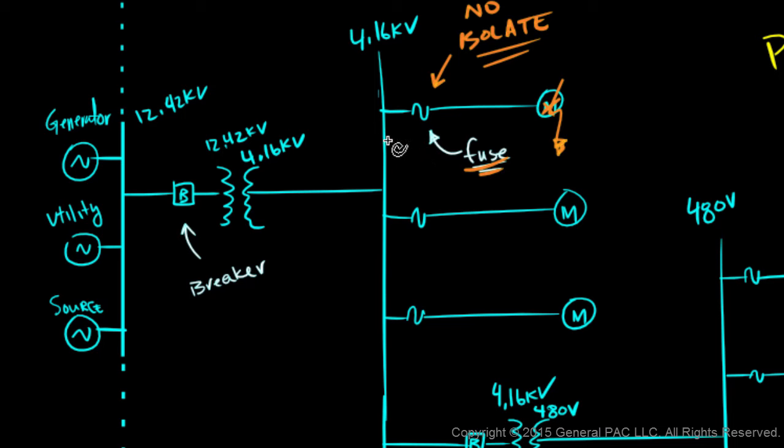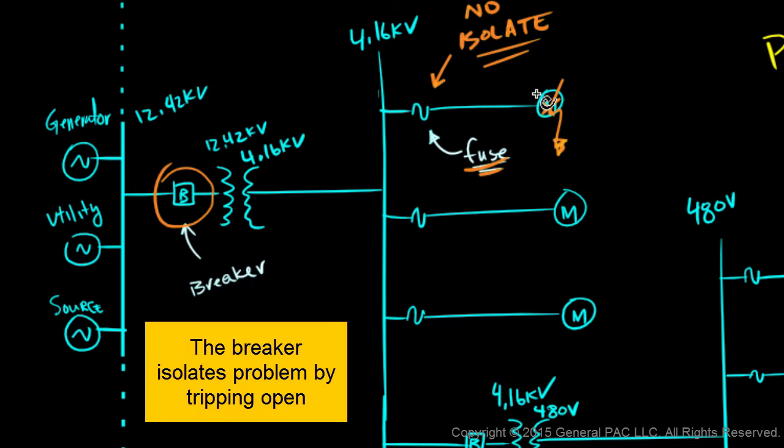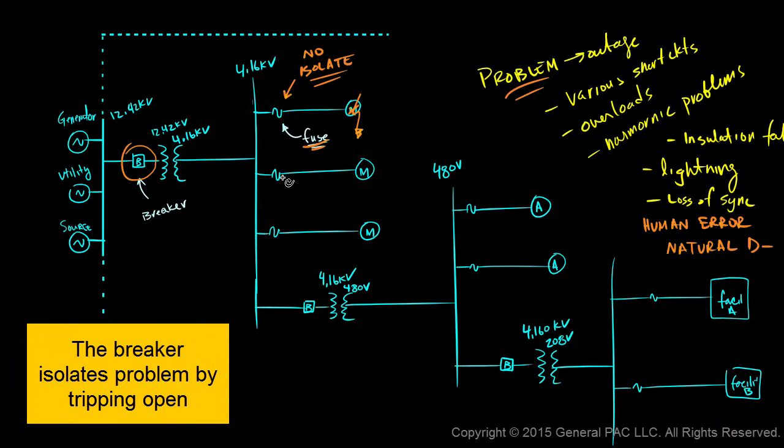Well, the next upstream device, which is this breaker, we should expect this breaker to isolate the problem. But what happens if this breaker isolates the problem? Well, what was a single problem on this single motor has now affected everything downstream. It has affected all the motors that are off of this 4.16 kV bus. It has also affected the 480 volt bus and the 208 volt bus.